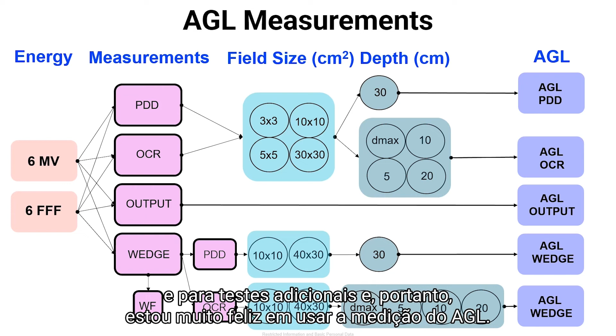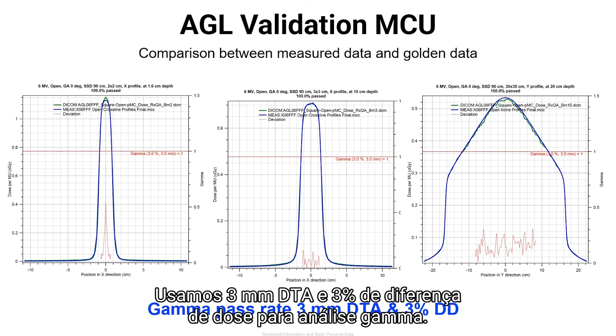So this is the validation of Monte Carlo system with AGL. These are the comparison between measured data and the golden data, and these are the gamma pass rates for PDDs. So these are the gamma pass rates for profiles. As you see, you use 3 millimeter DTA and 3% differences for gamma analysis.